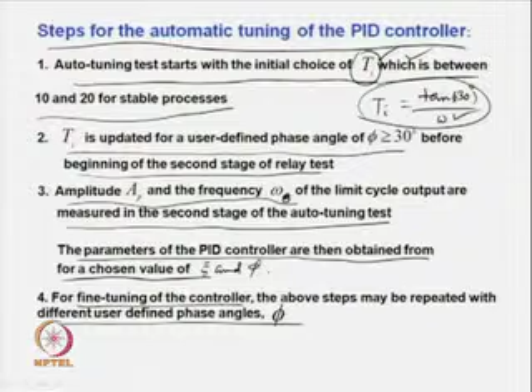Now, TI is updated for a user defined phase angle of phi greater than or equal to 30 degrees before beginning the second stage of the relay test, using the updation formula. Of course, TI is equal to tan of 30 degrees upon omega. So, omega is the frequency you obtain from the first test; substitute over here, then find TI, and substitute TI while conducting the second stage of the relay test. Amplitude AP and frequency omega of the limit cycle output are measured in the second stage of the auto tuning test. Those values will be used in the formula to find the PID parameters, and the parameters of the PID controller are then obtained from the set of formulae for a chosen value of xi and phi. Fine tuning of the controller, if necessary, can be done with different user defined phase angles phi. We will go to the simulation study now.